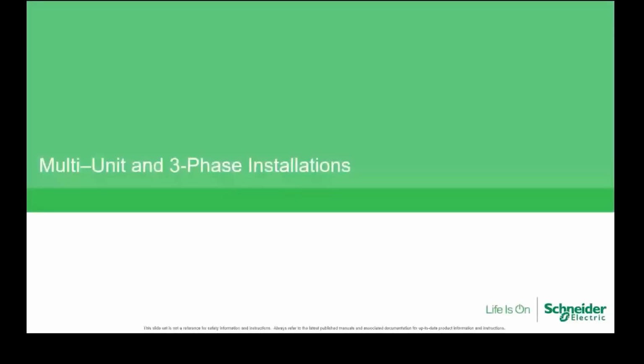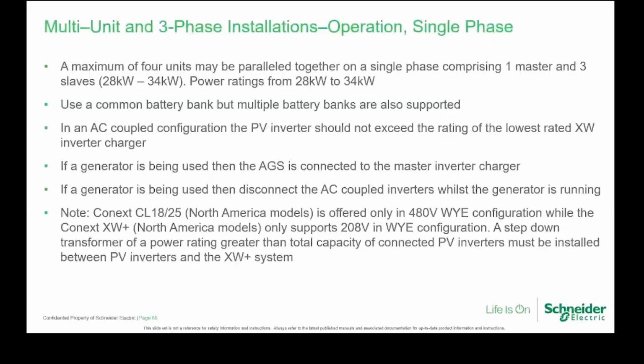Now, a quick look at the multi-unit and three-phase installation. Basically, for a single phase, you could have a maximum of four units in parallel, with one master and three slaves. That's up to 28 kilowatts, 34 kilowatts. Use a common battery bank, but multiple battery banks are also supported. In an AC couple configuration, the PV inverter should not exceed the rating of the lowest rated XW inverter charger. If a generator is used, then the AGS is connected to the master inverter charger. If a generator is used, then disconnect the AC couple inverters while the generator is running, like I said before.